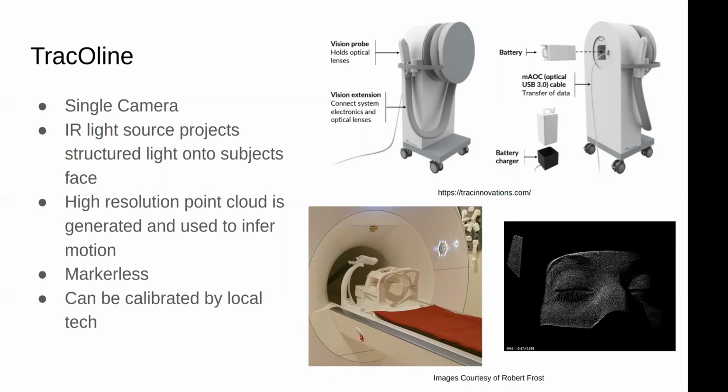So that's always one of my concerns: faster is good if you can get it fast without motion, but faster is actually bad if they're moving. Absolutely. Especially with multiband and GRAPPA, they have a reference acquisition, and if they move during the reference acquisition, that's critical. Everything depends on it.